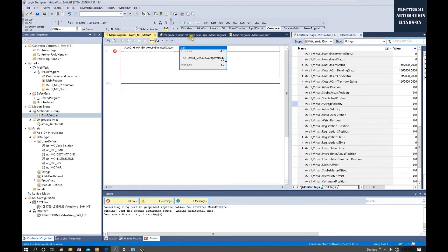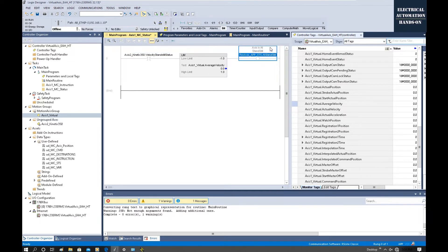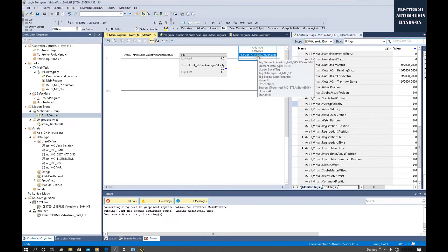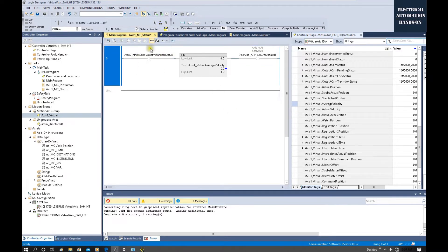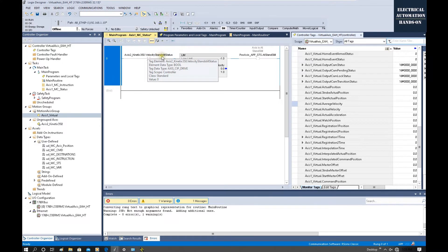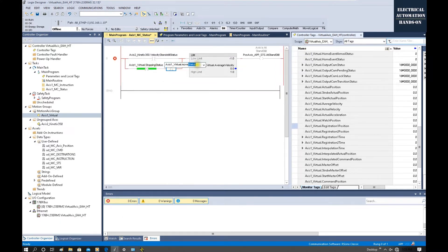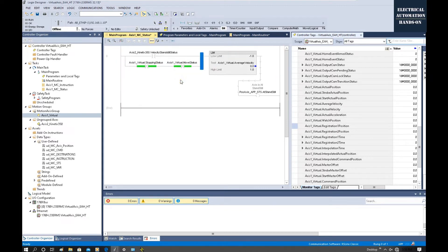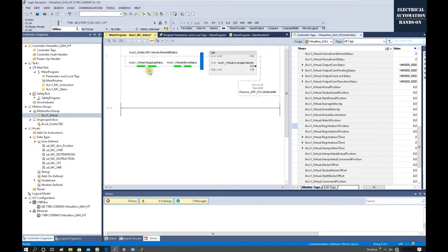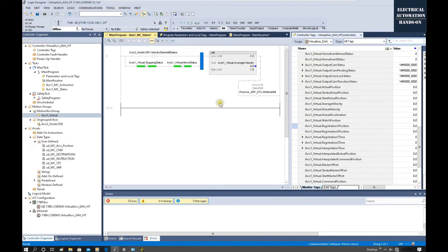So the lower limit could be set as minus 1.0, this is speed unit. The higher limit could be set to 1.0. This could be a very narrow window. And for the result, we can output to PositioningAxis.Application.Status.AtStandstill. We will output our defined variable. Since this standstill comes from the actual CIP drive, and we're using the virtual axis to replace this standstill signal, alternative way we can grab another signal from the virtual axis. It has a Stopping Status and the Move Status. So basically, if the Move and Stopping status are zero, combined with this average velocity almost zero signal, this basically means this virtual axis is at standstill, at stop status.